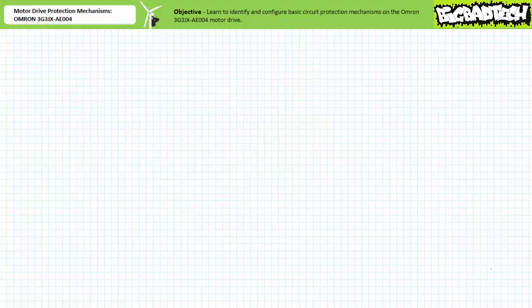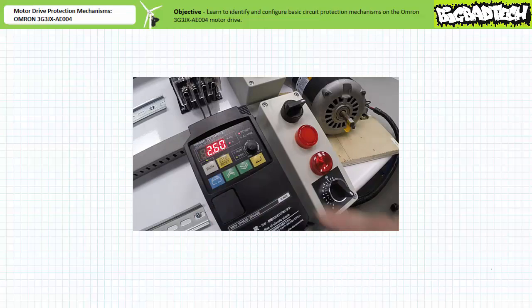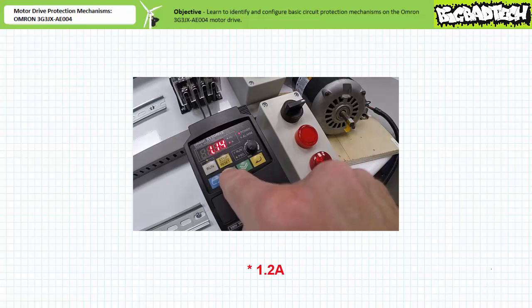Let's adjust communication parameter C041, overload warning level, to an unusually small level to trigger the warning even during an unloaded condition. Note the overload warning level is exactly that — a warning and not an indicator of an actual overload where the drive faults out or takes action to correct it. Navigate to communication parameter C041, overload warning level. The default warning level is the rated output of 2.6 amps. Decrement this value to 1.1 amps and press enter to save it.